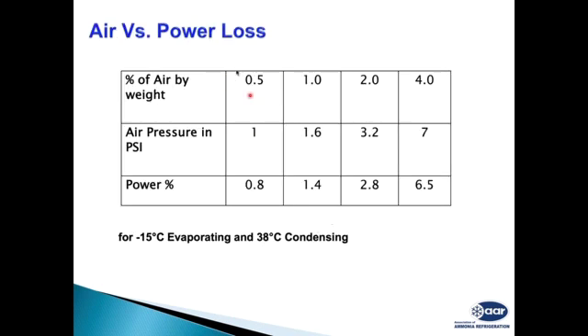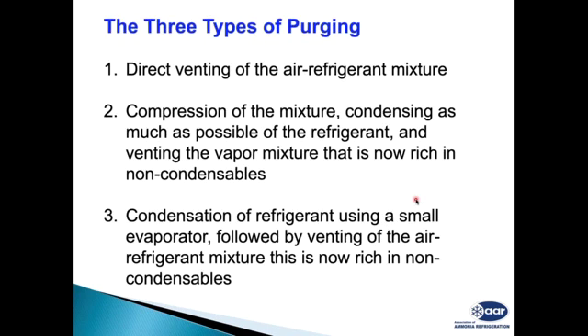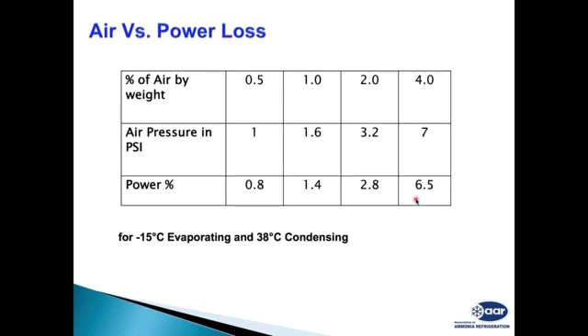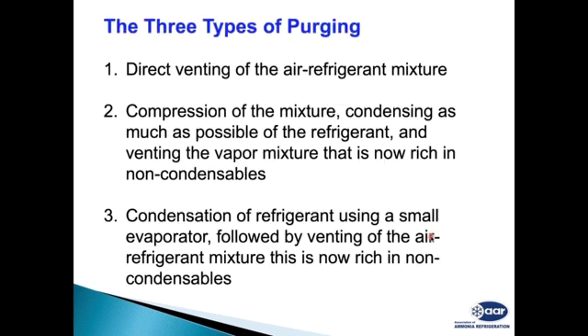So typically, if we have 0.5% air in our plant, the pressure can increase by 1 psi, and power consumption can go up by 0.8%. If we have 4% air by volume in our plant, the power consumption will go up by 6.5%. This is a very high penalty to pay for our running plant, because our refrigeration plant is continuously running. And if the air remains in the system, this directly affects the power of the refrigeration plant. And if you add the losses of maintenance, oil failure, and component failures, it becomes very high.